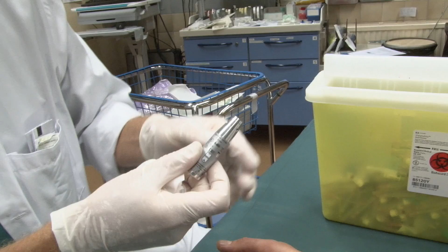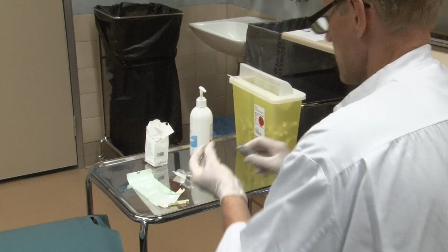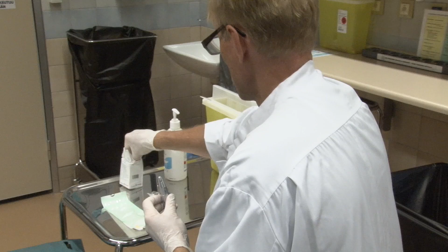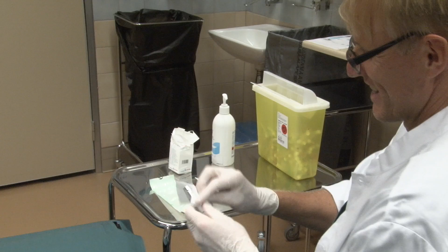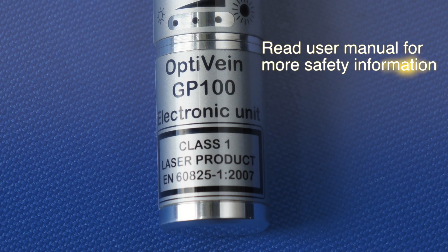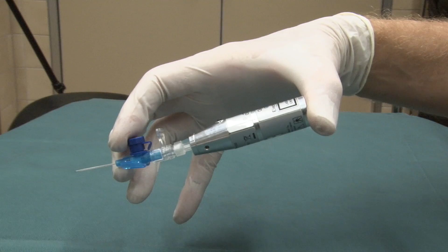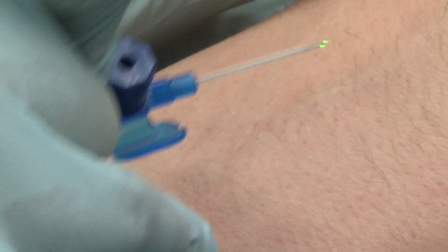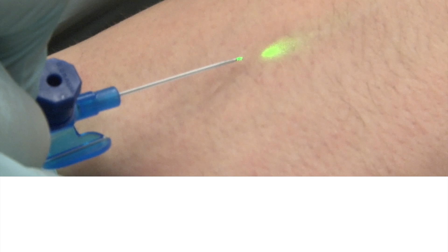OptiVein electronic unit is a multiple-use device. It should be disinfected every time, before and after use, by applying an appropriate disinfecting wipe in accordance with institutional SOPs, for example, alcohol or chlorhexidine wipe. OptiVein IV catheter, when mounted onto activated OptiVein electronic unit, is a low-risk Class 1 laser device. The laser light is so weak that it cannot cause damage to skin tissues, veins, or blood.